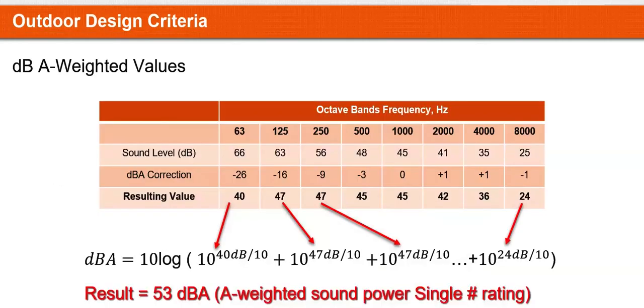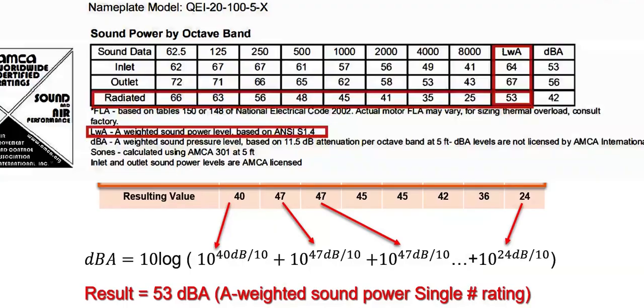To explain in detail what that looks like, I have the cut sheet of a mixed flow fan from a particular manufacturer. We're going to focus on radiated noise, but this could be done for the inlet sound power levels and discharge sound power levels for that particular fan. Just because we're focusing on radiated to talk about panels doesn't mean that you should not treat the discharge or inlet. The main message in this session is that the moment you treat one or the other, it is going to have an impact on the outlet sound power levels or radiated sound power levels. It's not just one path. You're going to have to treat all of them.